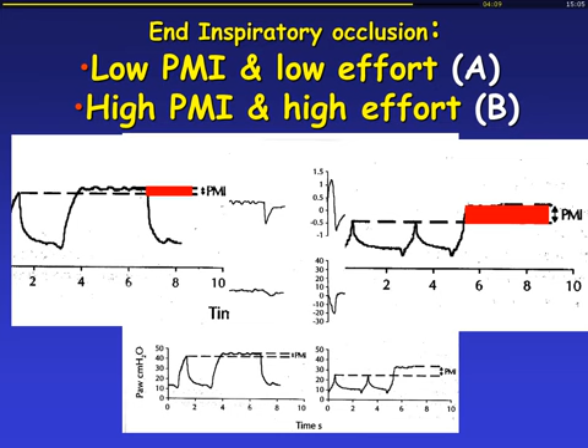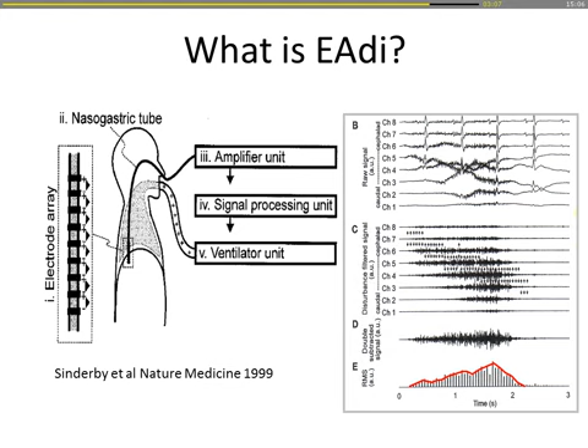A more sophisticated approach is using the diaphragmatic activity. The electromyography of the diaphragm is used to drive the ventilator in NAVA, neurally adjusted ventilatory assist. You can get the electromyographic signal under any condition. And you can measure the electromyographic signal also during pressure support, as an example, or during CPAP. The electromyographic signal is proportional to the force, to the recruitment of the fibers of the muscles. And here we are talking about the diaphragm.